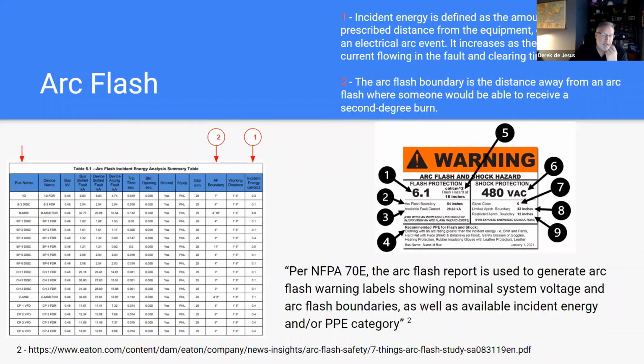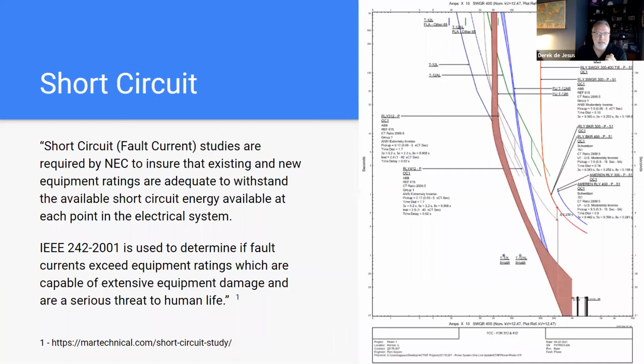Yeah, so what you're probably talking about is the series, the short circuit coordination rating of the gear. And what that gets into is back on this table here, where you have the short circuit rating of that equipment and the device that sits within that equipment. Most of your incoming gear will be either 100K AIC or perhaps 65K AIC rated gear. What that means is that gear, and I think it says it actually right here, are to ensure that the existing equipment ratings are adequate to withstand the available short circuit energy, right? So that's the gear. And I think what we're talking about here with Tom is that the breakers and the devices within that gear are also rated accurately to serve those loads within that piece of equipment.